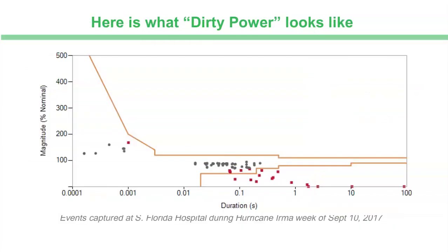This is another example just to give you a comparison. This is what dirty power does look like. This is an actual event. This shows power quality events during the week of Hurricane Irma in Florida. All of those events shown as red dots are ones that are at or outside of the acceptable range. So certainly equipment damage and disruption would be expected looking at something like that.